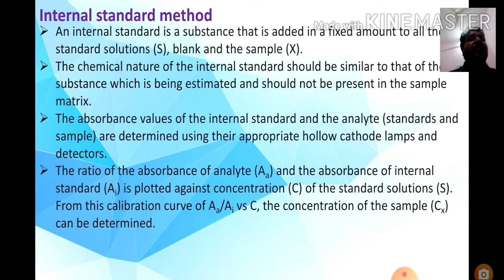The absorbance values of the internal standard and the analyte are determined using their appropriate hollow cathode lamps and detectors. Then the ratio of absorbance of analyte AA and the absorbance of internal standard AI is plotted against the concentration of standard solutions S. From the calibration curve of AA upon AI versus C, the concentration of the sample Cx can be determined. So this is the internal standard method calibration curve.